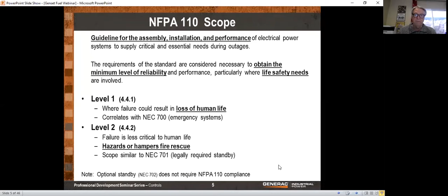The code says for level 1 installations—again, we're talking about emergency life safety—in locations where the probability of interruption of off-site fuel supplies is high, on-site fuel storage, or an alternate energy source sufficient to allow full output of the EPSS for the class specified, shall be required.